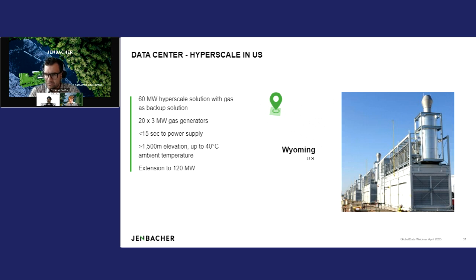As a third point, the same footprint as a diesel generator and the same integration as he had with a diesel generator, so there was no need to change any UPS system or add battery storage capacity, since we replicated the same start time. We're also going to extend the plant with more megawatts over time. Very interesting too, as Markus mentioned before, this site is at very high elevation and high ambient temperature, and we have no derate — very unique for gas engines compared to, for example, turbine technology.